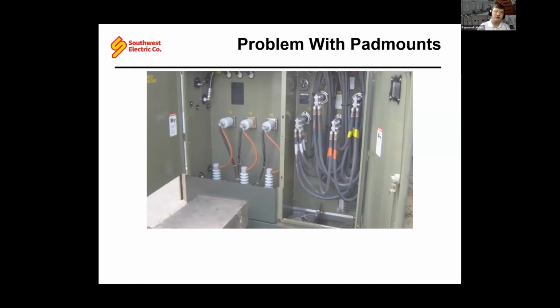A typical pad mount transformer, and there are many, many, many of them in the distribution realm, is by definition tamper-proof. And so everything is locked into a cabinet, and everything is accessed in that cabinet, including the power cables. So you might notice that your sample valve happens to be right here, right below all your energized power cables. And obviously today you'd have to suit up in your proper PPE. Hopefully the incident energy rating of this pad mount does not exceed 40 calories per square centimeter. Otherwise you wouldn't be able to access it at all while energized.